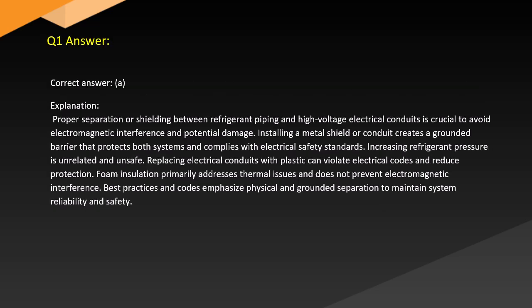Answer. Correct answer, A. Explanation. Proper separation or shielding between refrigerant piping and high-voltage electrical conduits is crucial to avoid electromagnetic interference and potential damage. Installing a metal shield or conduit creates a grounded barrier that protects both systems and complies with electrical safety standards. Increasing refrigerant pressure is unrelated and unsafe. Replacing electrical conduits with plastic can violate electrical codes and reduce protection. Foam insulation primarily addresses thermal issues and does not prevent electromagnetic interference. Best practices and codes emphasize physical and grounded separation to maintain system reliability and safety.